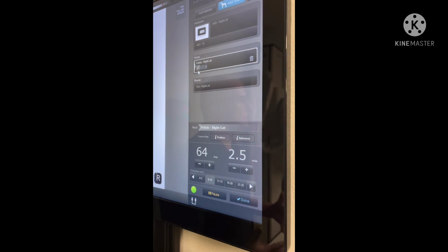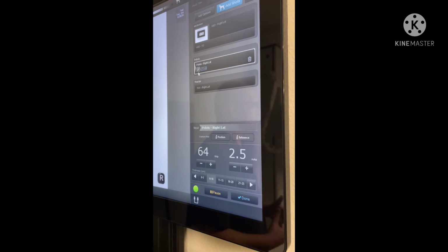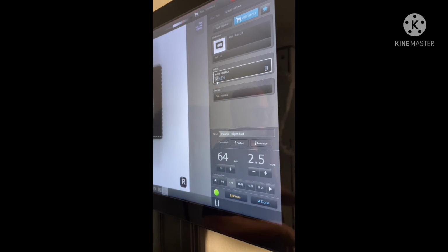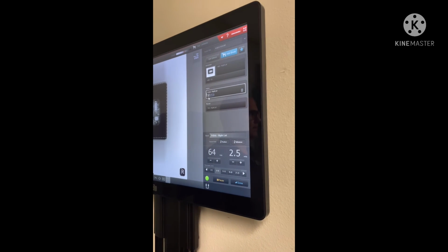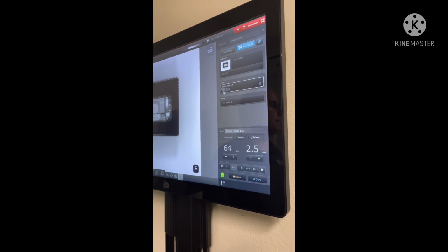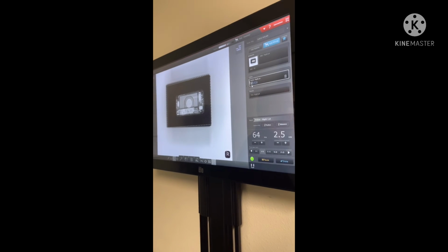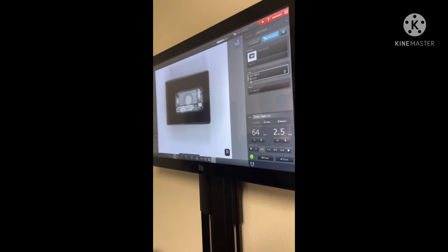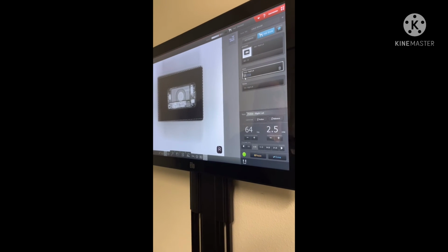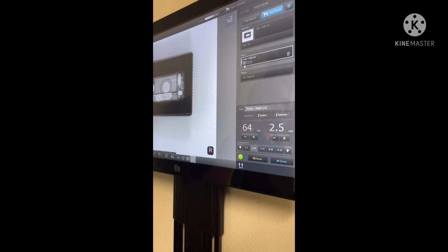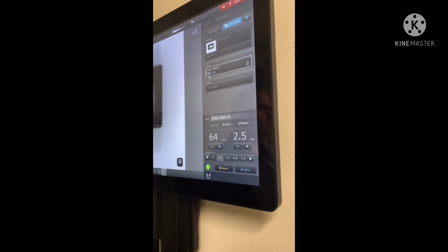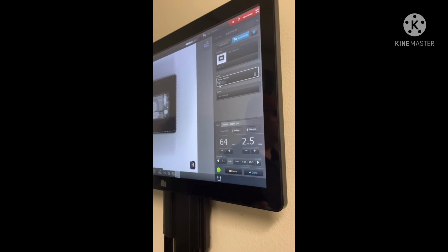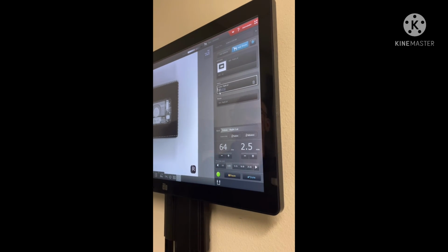What it's going to do is apply an extra layer of filtering to kind of reduce all that fat scatter and bring out the contrast in the bone. Just really make the image look better. Okay? If you forget to check the box, you take the image and you're like, oh, that doesn't look good, we could do it again but better, just do retake and then check the box the second time when you do it. So you do have to check it before you take the image, but if for any reason you forget, just do retake. Not a big deal.